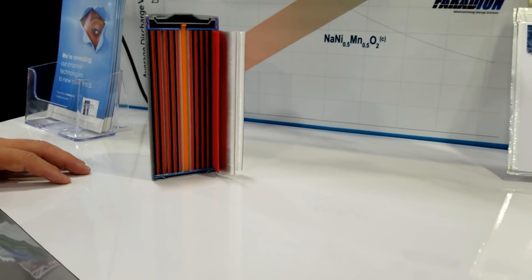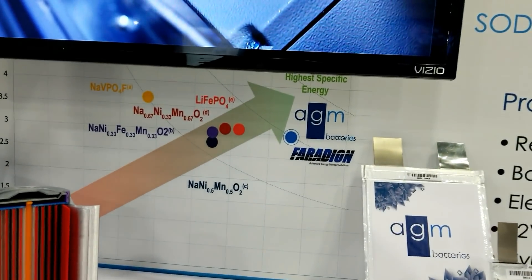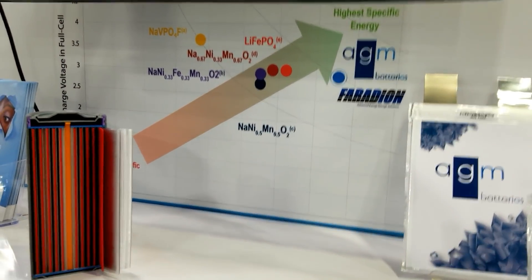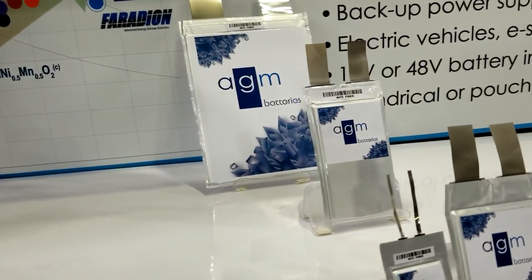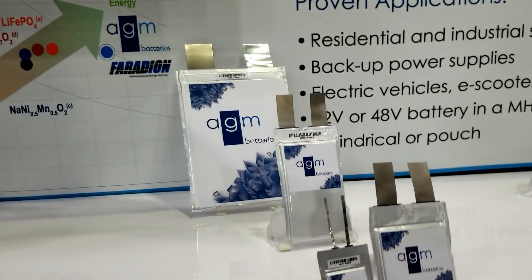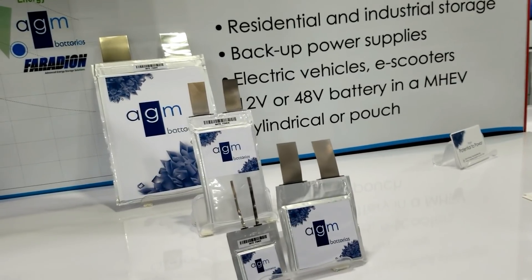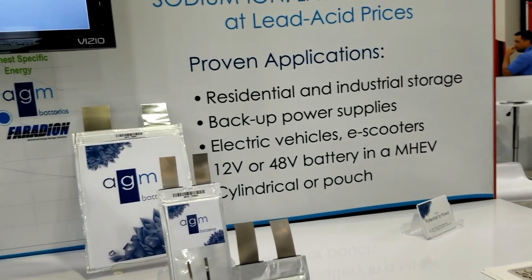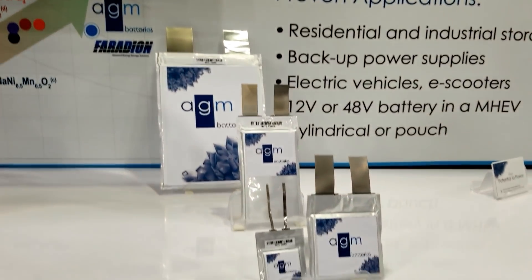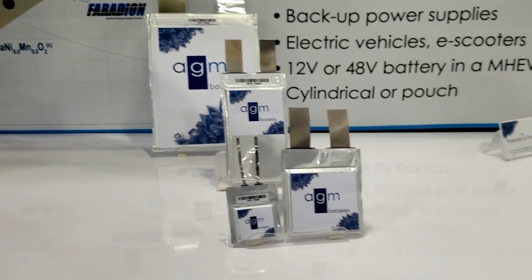What's the nominal voltage on the sodium? It ranges from 12 volts to 48 volts a pack, built effectively by series wiring. The individual cells will be all different voltages, depending on the density of the material and how many layers of material. So that's different from lithium ion, which is always going to be 3.6 volt nominal. There's a whole range of different energy and capacity coming out of the cell design.